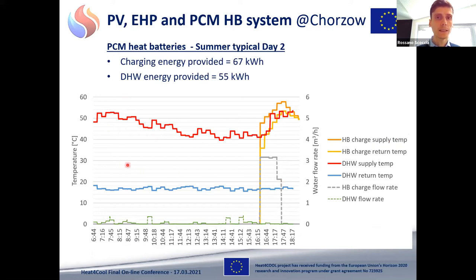Here, the focus is on the PCM heat batteries. So here you have one day, and you see that in the first part of the day, until 4 p.m., we managed to use the energy stored in the PCM to produce the domestic hot water. When we reach a minimum threshold of 40 degrees C, we start to charge the PCM batteries again, and we can simultaneously charge and discharge the heat batteries. So here you see how we are charging the heat batteries, and at the same time we are producing hot water. In blue, you see the temperature of the water coming from the water main, and then the dashed lines are the flow rates of the heat batteries or of the heat pump which charges the heat batteries.